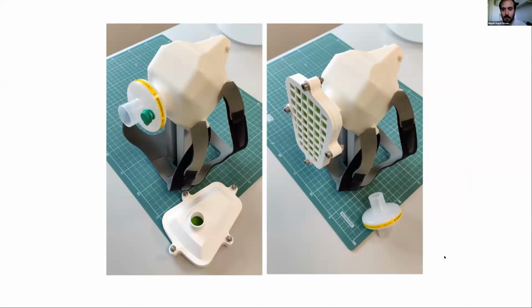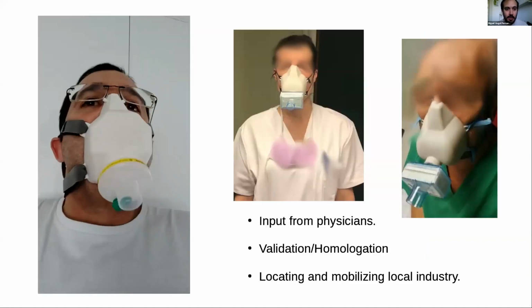Here you can see the prototype in FilaFlex. This is flexible, but it is not the way to go for ER rooms, because with FilaFlex and every other additive manufacturing, you know there are some defects and tolerances, and there is even the issue of porosity at the micron scale, which I will talk about in the last slide. It's very negligible in a low risk scenario, like for example a police officer or a supermarket, where that can be good. But in an ER room, where the density of viruses in suspension is very high, because they are aerosols, colloids in suspension, there is no option to take any risk. So this is only the prototype, and we need to move to injection in rubber, silicone, or any other material like this. Here you can see the proof of concept.